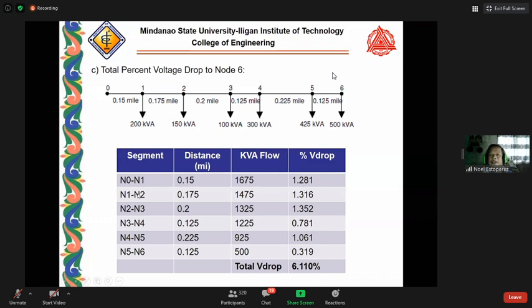So between N1 and N2, we now have 0.175 mile. We subtract 200 from 1,675, which gives 1,475. So the result here is 1.316. Going farther, from N2 to N3, we have 0.2 miles. Subtract 150, and it becomes 1,325. So the voltage drop at this point is 1.352. Okay? Then going N3 to N4, N4 to N5, and up to node 6, we can now compute the total drop at this point. So the total drop at this point will be 6.110.